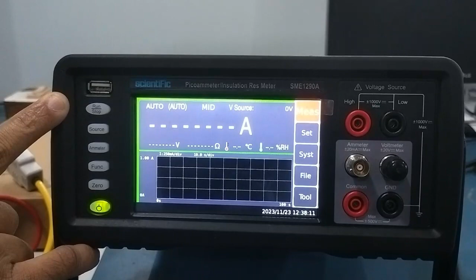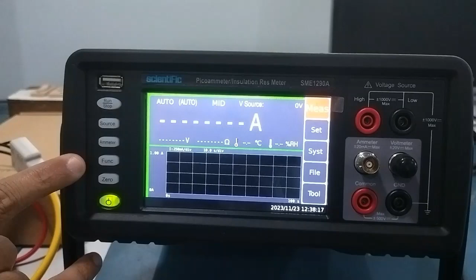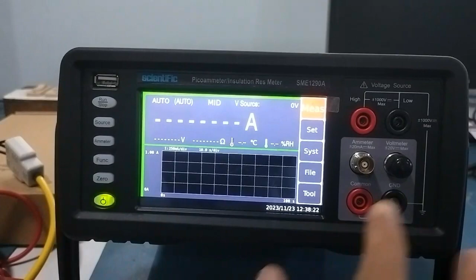These are the menu key buttons to run and stop the instrument, to source the voltage, to start the ammeter, to select the function, and to zero the readings. These two ports are for the voltage sourcing plus minus 1000 volt. Here this BNC is for ammeter plus minus 20 milliampere. This is for voltmeter plus minus 20 volt, and these are the common and ground terminal.